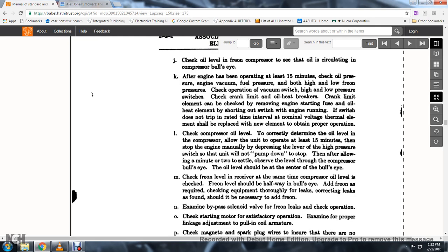l. Checking the compressor oil level: to correctly determine the oil level in the compressor, allow the unit to operate 15 minutes, then stop the engine manually by pressing the lever of the high pressure switch so the unit will not pump down to stop. Then, after allowing a minute or two to settle, observe the level through the compressor bullseye.